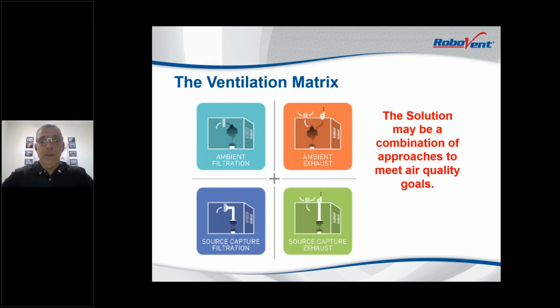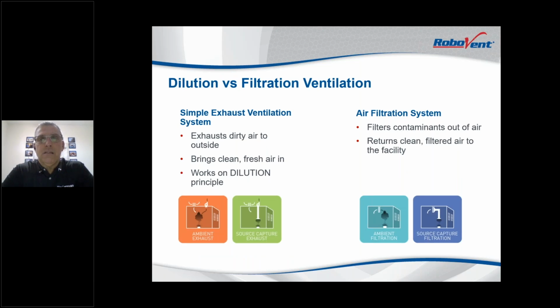So the preferred method is filtering the air, and that's what this slide presents. With dilution or exhausting the air to the outside, you're dumping dirty, unfiltered air to the outside, and you're bringing fresh air in. But typically, with those extreme temperatures, you'll have to temper that air one way or the other. Air filtration systems are by far and away the best. It's the best in class. You can filter the air and return that air to the building. It does not upset your HVAC, heating, or cooling balance in your facility, and you are returning the clean air to the plant. You don't have to worry about permits to operate or permits to install as you dump unfiltered air to the outside environment, outside of your facility envelope.